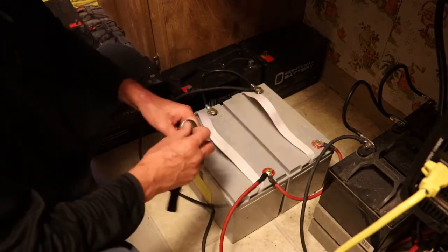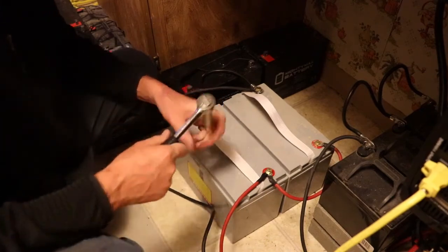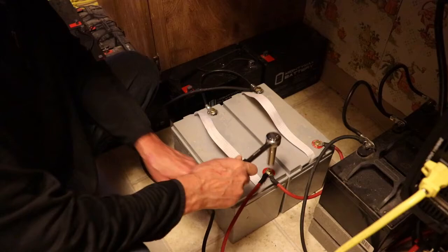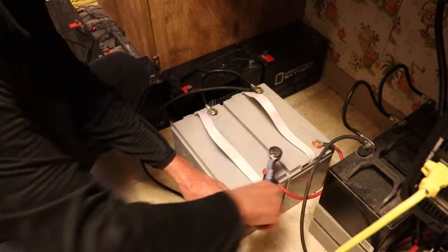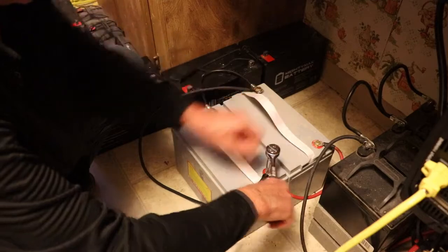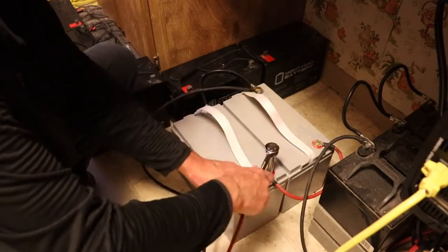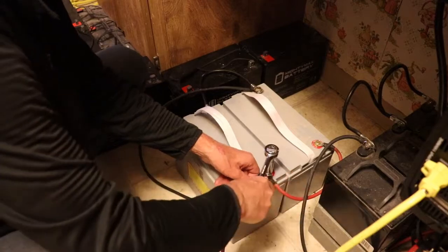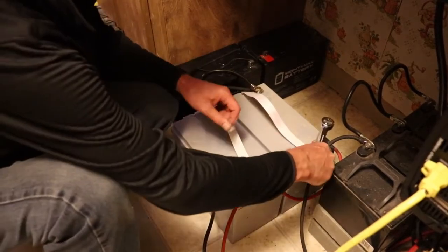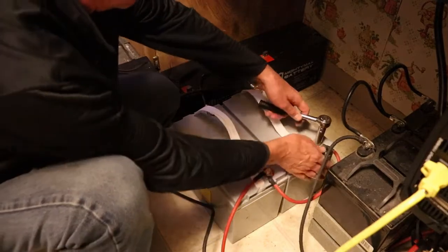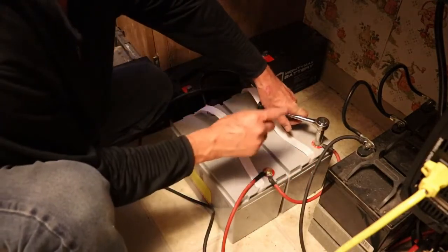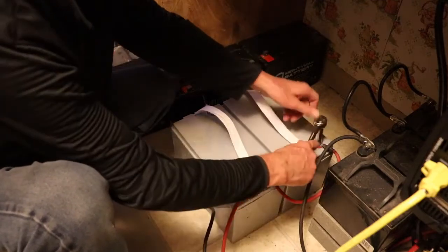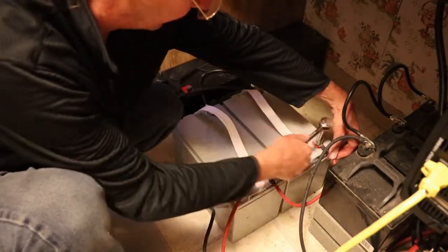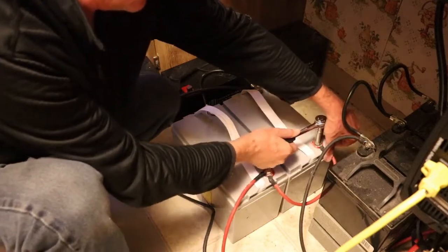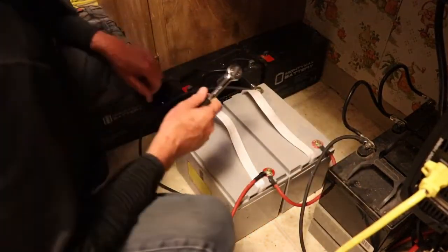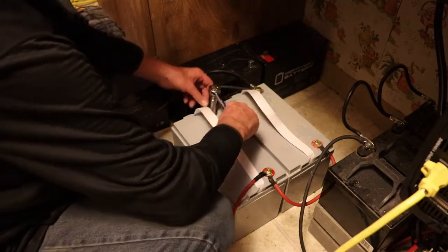So I'll wrench down the positive leads first, and make sure you use an insulated ratchet just in case, folks. Well, the fact that I'm touching that, not going to make much difference, is it? Now if I was to connect these in series, I would go positive, negative, positive, negative, just like it sounds. So, and I have this other system turned off also that's right next to it. It's a lead acid system, because I want to reduce the shock hazard.